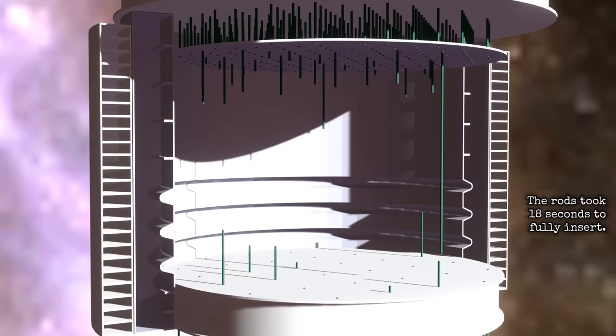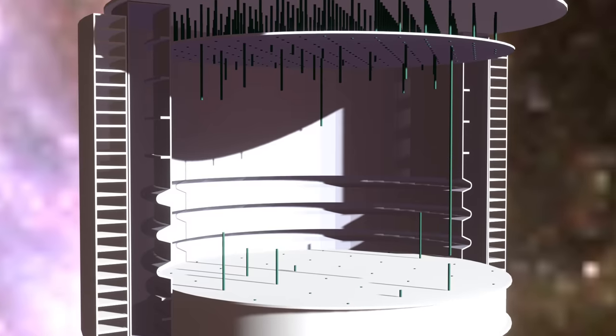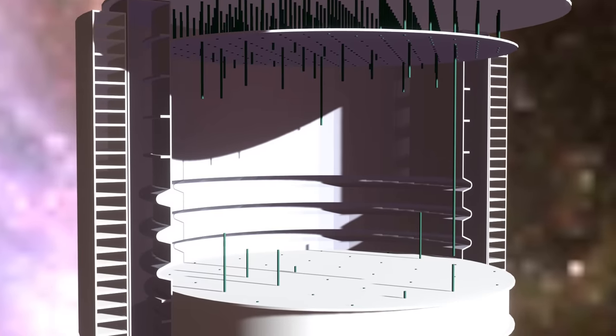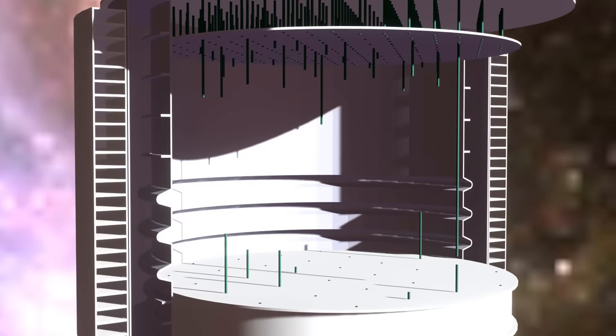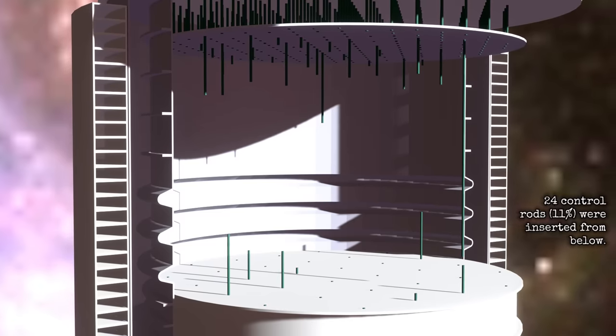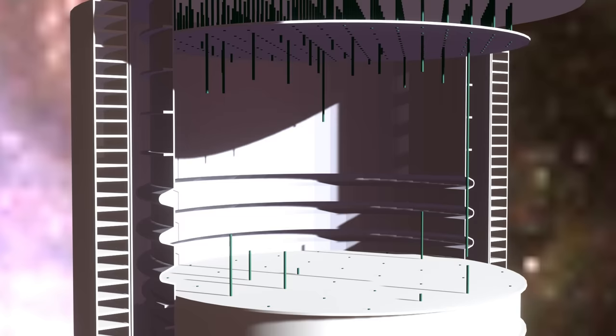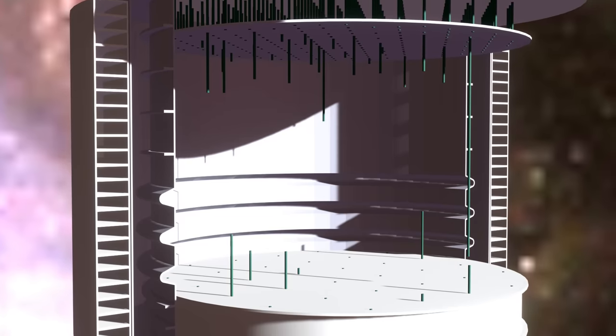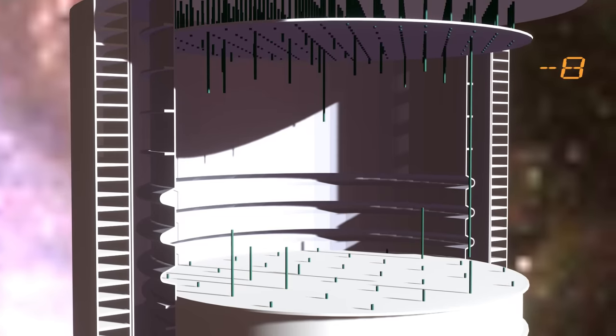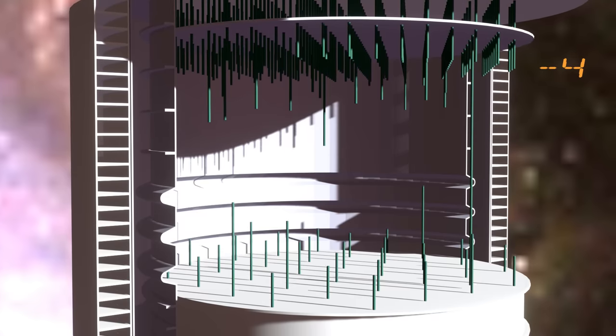The control rods were in this configuration when the AZ-5 was pushed. It is frightening that there was just one rod fully inserted. At no time should the core have had less than the equivalent of 26 rods active, but on this evening, it had almost none because of the misguided attempt to counterbalance the xenon poison. The reactor had been pushed too far.